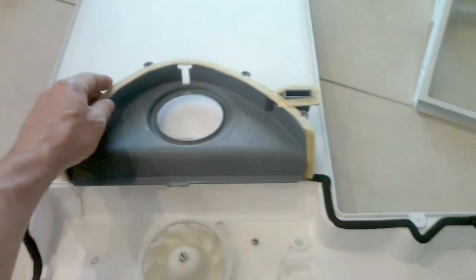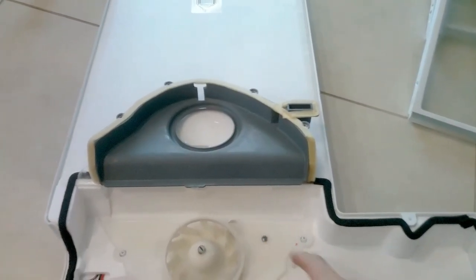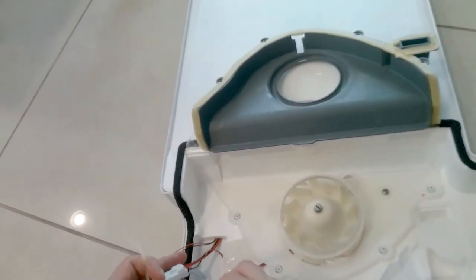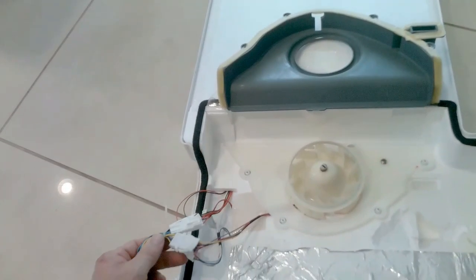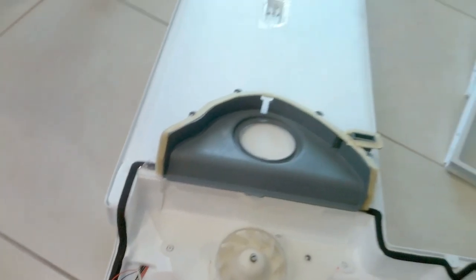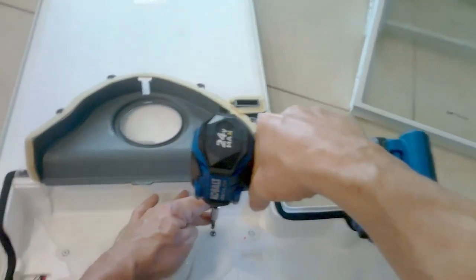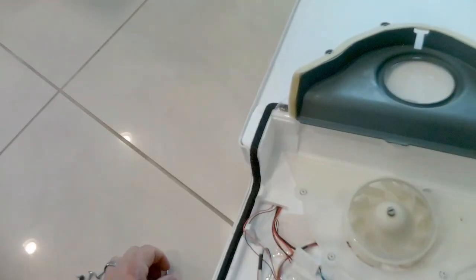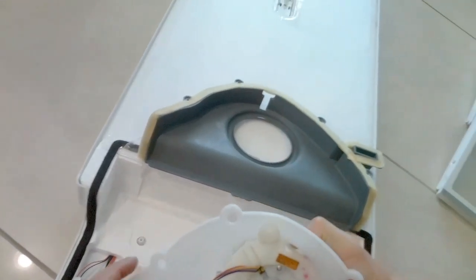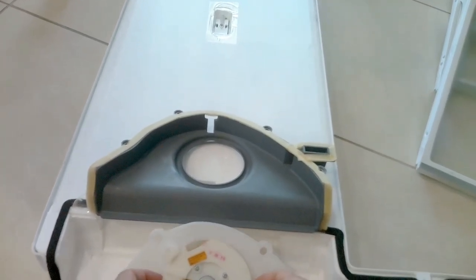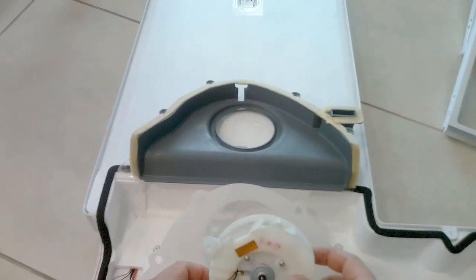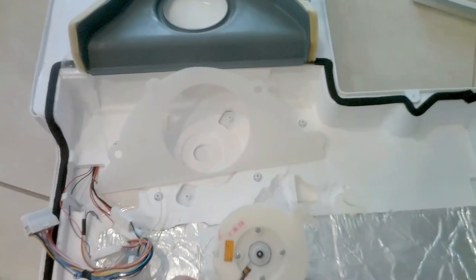To remove all the Phillips screws, just turn it over just like that. Then you have one Phillips screw that holds this into place, and then you got your harness here, which is basically clip off and clip on, real simple. Let me show you exactly how to do this. This is the only screw that holds this into the evaporator cover, and then you just pull this straight off. The fan motor just pulls right out and has the three wires: two for the input power and one for the feedback signal, which is the error code you get when it doesn't perform correctly.